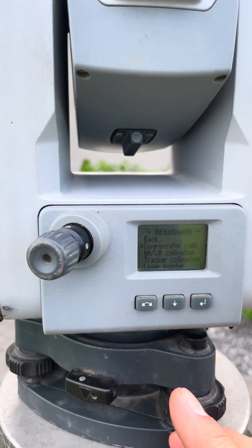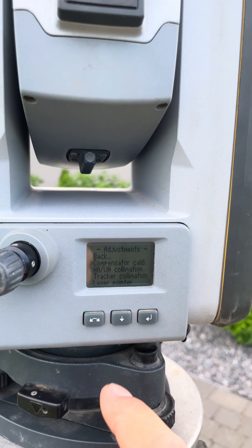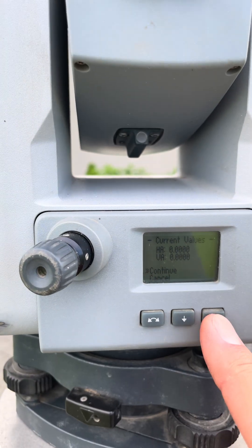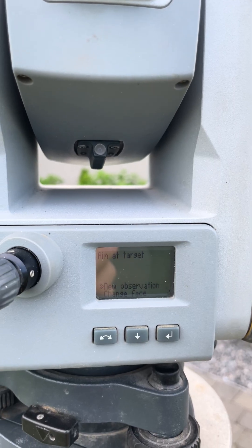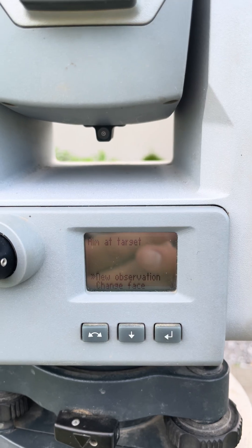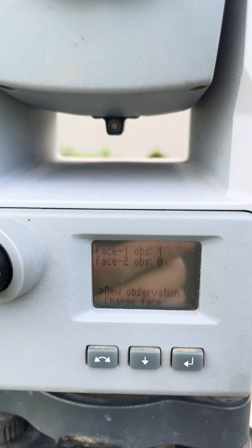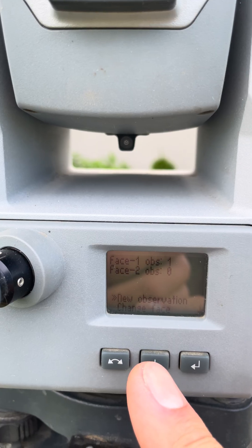Now we can go to Horizontal and Vertical Collimation Error. Let's hit that and basically follow the prompts. Current values are zeros. Let's aim at the target and perform this — I'll pause so I can aim at the target and then hit New Observation for face one.